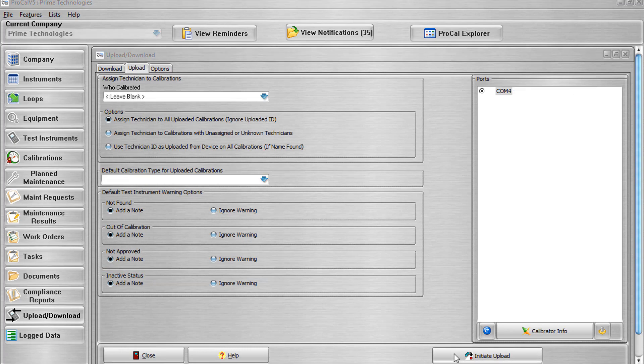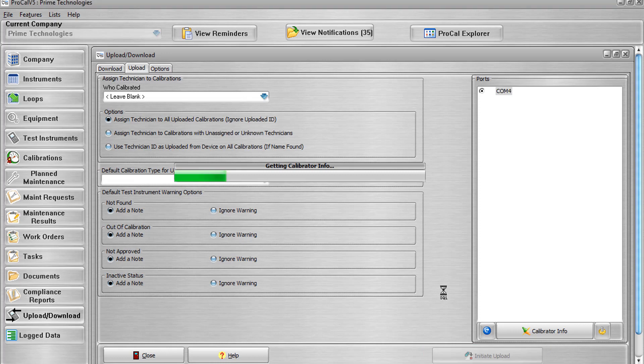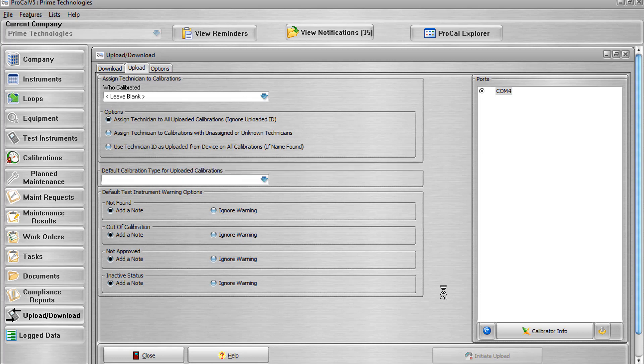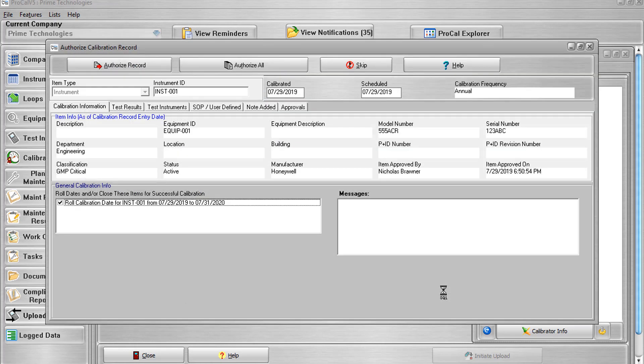After all of your upload settings have been set, you can select the Initiate Upload button to upload your calibration. Selecting this button will upload all result data from the connected calibrator, skip over any non-ProCal V5 result data such as aborted tasks with no calibration results, identify all valid results as being an instrument or loop and identify the test point group number for each one, add the calibrator and any auxiliary equipment found to the list of test instruments used, check for the calibration due date of the calibrator and other auxiliary test equipment and construct warnings if applicable, process all test points and readings according to the item's default test point groups, and build a new calibration record. If authorized, the program will add the displayed record as a new, unfinalized calibration record.